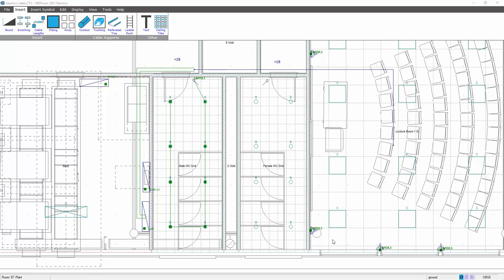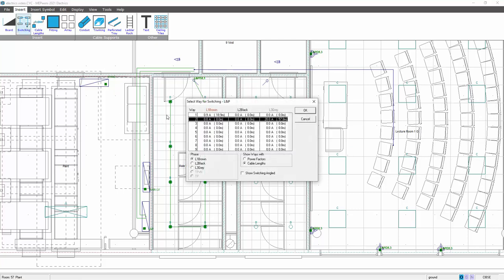So these now have cable lengths associated with them, so that when you go to the switching and select the board again, you have a cable lengths option. You can see here it puts the cable length against each of these circuits. If it's a three-phase load, then what it will do, it will put in a cable length on the lead phase.